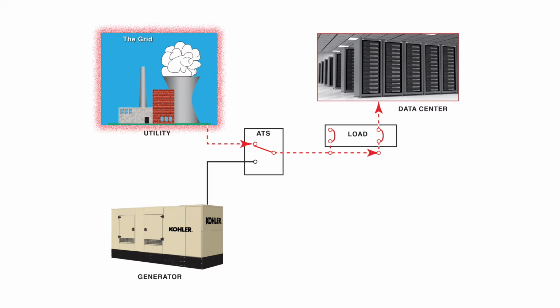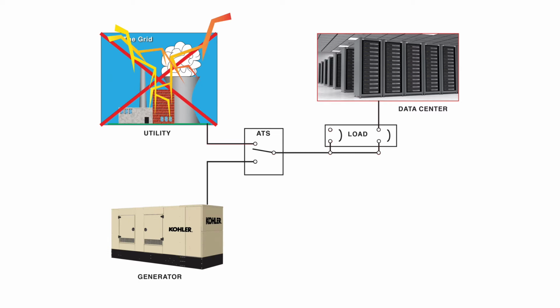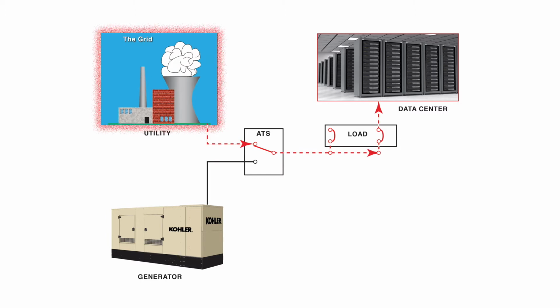Power normally flows from the grid. When the utility fails, a sensor starts the generator. When the set runs up to speed, the load is transferred to the generator via an automatic transfer switch. The generator continues to supply the load while the utility is offline.